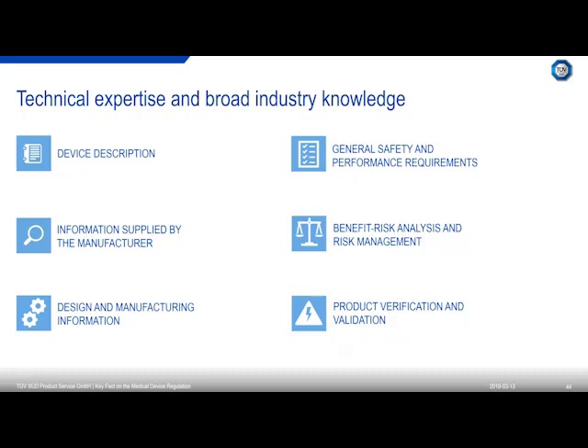and that this needs to be part of your technical documentation. Then we have a lot of design and manufacturing information, which we didn't have in that detail before. So the third section of this annex requires a lot of information here, information allowing the design stages to be understood, for example, and also supplier information is becoming very important. Then we have the general safety and performance requirements, which is the new term for the essential requirements. This is pretty straightforward. So if you fulfill the Annex I, then you have to show compliance to each requirement of the Annex I by evidence, typically a report, and that is information you might provide here. Then there needs to be a benefit risk analysis and risk management, which is also nothing new. So risk management is not really affected by the MDR because it's already there.